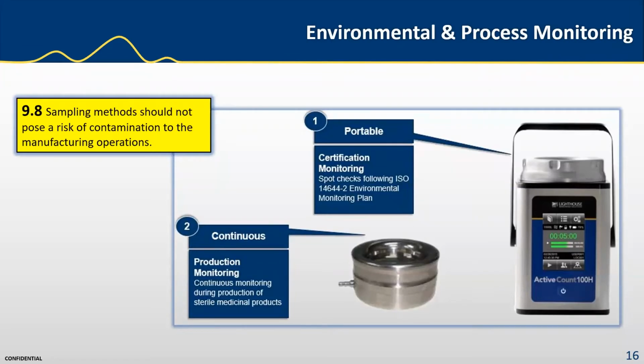Sampling methods should not pose a risk of contamination to the manufacturing operations. This is section 9.8. So the material of construction and the ability to clean and sanitize the measuring equipment should be assessed. For example, the portable air sampler should have a HEPA filter exhaust. The base plate and sample head should be easily removable for the autoclave. Interface should be intuitive, and a touchscreen is more desirable rather than having buttons and more switches to press. The design of the unit should not allow the introduction of particle traps. Buttons and switches that stick should be avoided. Sample heads and bases for continuous samples should be stainless steel so they can be easily autoclaved. And here we have 2 examples, a portable air sampler and a sampling head which attaches onto a continuous viable system.